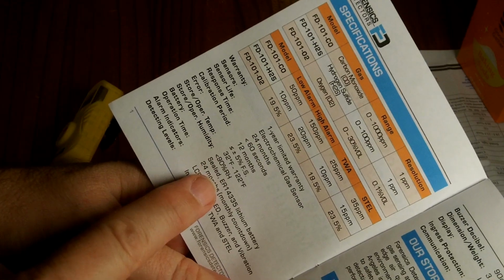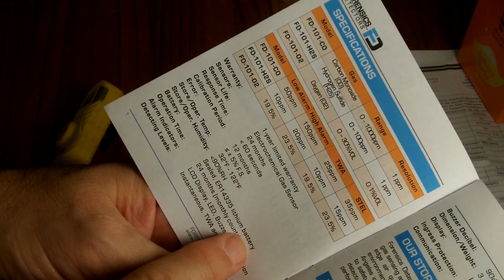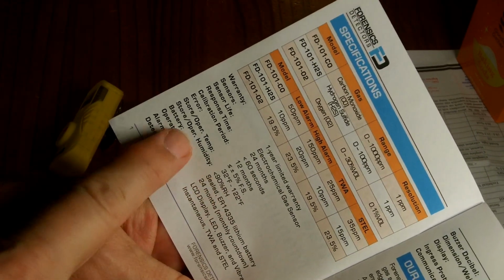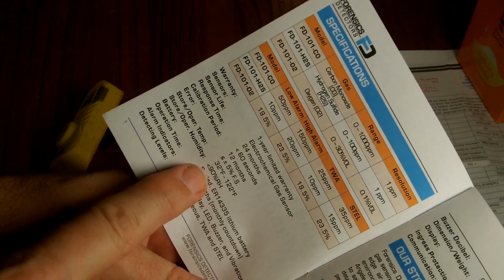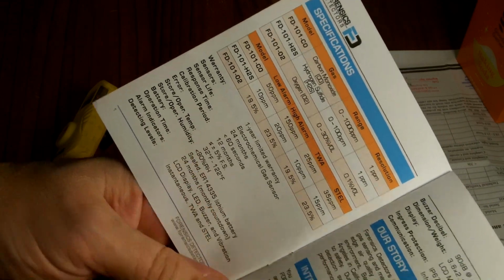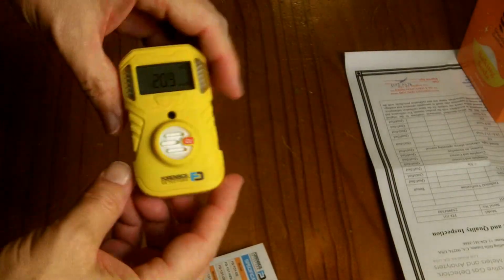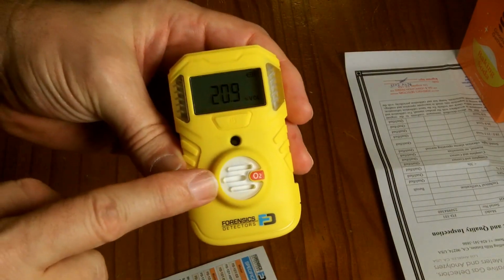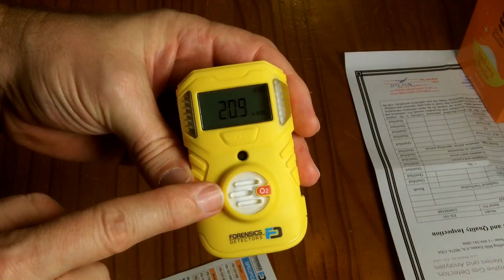So it says a sealed ER14335 lithium battery. There is a limitation that you should store and operate at less than 90% relative humidity. I believe if the relative humidity is higher than 90%, the electrochemical sensor may not be as accurate.